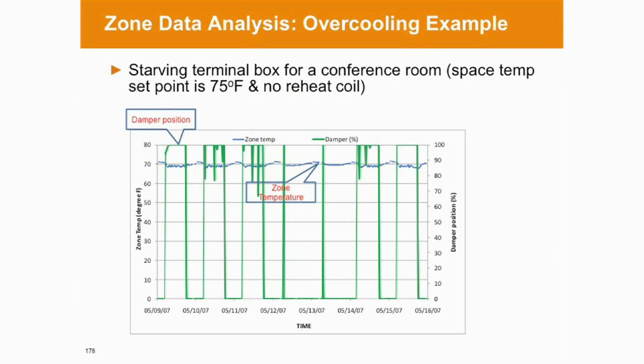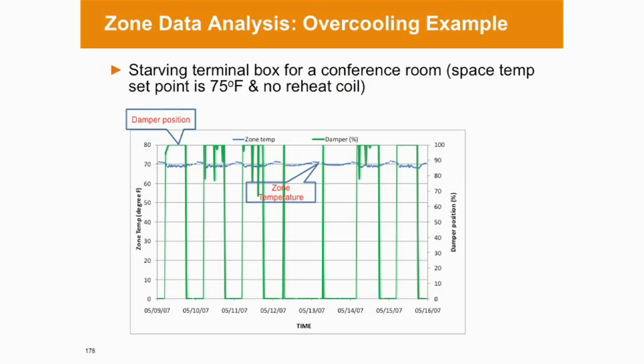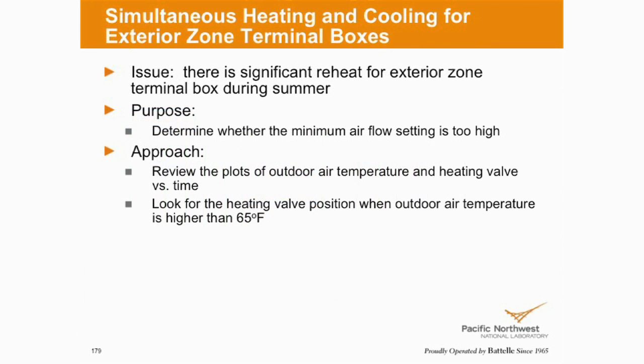So this is an example of a starving terminal box for a conference room. So you see the space temperature is set to 75 degrees, but the actual zone temperature is about 70 degrees, because just like I said, there's two control loops. One is control the zone temperature, but another one is they still have to maintain the minimum airflow set point for that space. So that's why that zone has been cooled down to like 70 degrees. So that's opportunity to change adjust the set point.